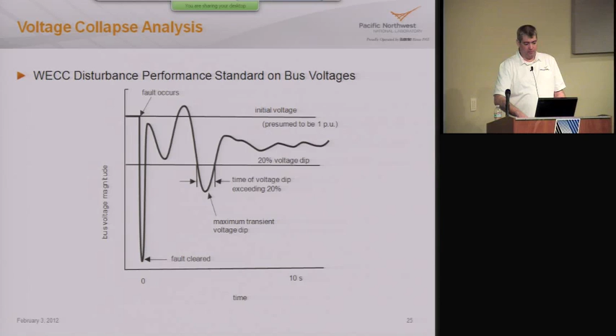Then we looked at voltage stability. The scenario that we looked at here is if you drop the load, the voltage is going to go up. And then the automatic voltage regulators and the tap changers are going to bring that voltage back down to nominal. Then could you reconnect the load after the voltage is brought back to nominal and try to drive it into a low voltage condition? So that was the scenario here. This plot is just the standard disturbance performance requirements for WECC, and this is the result of our simulation.